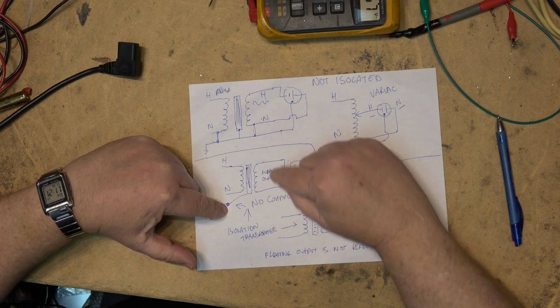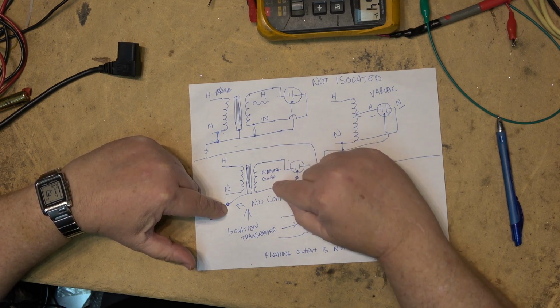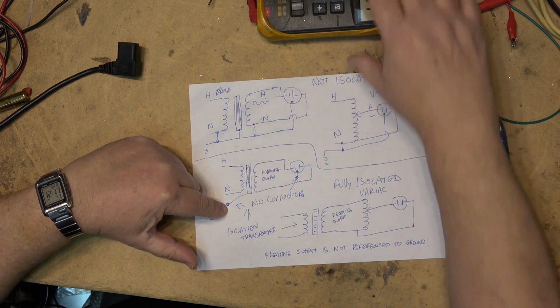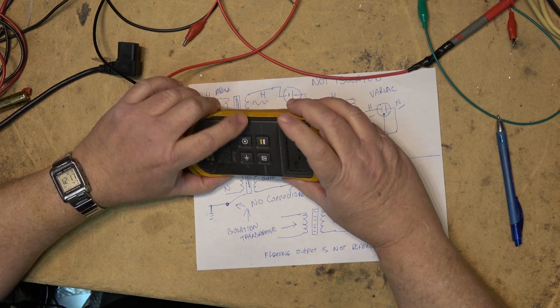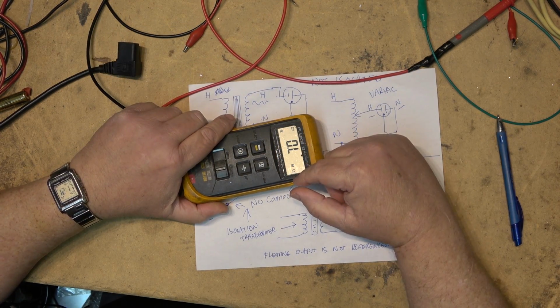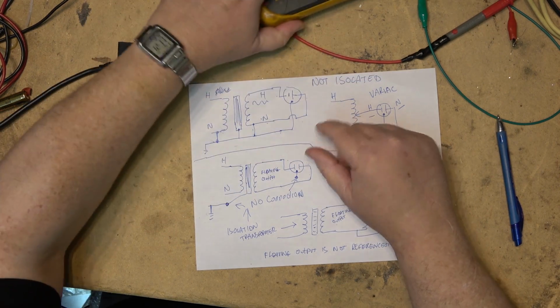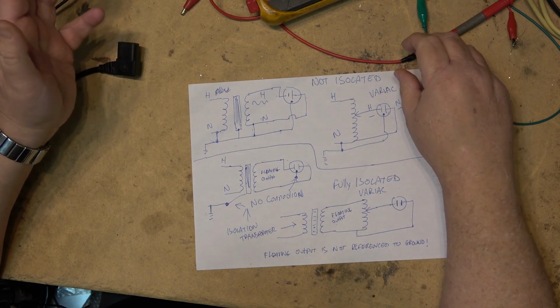Between ground and any of these, it will be an infinite reading. There will be zero. It'll say OL if it measures anything when you're in ohms mode. If it measures anything other than OL, then it's not an isolation transformer. It has a ground reference somewhere along the line. And I can even show you that here.